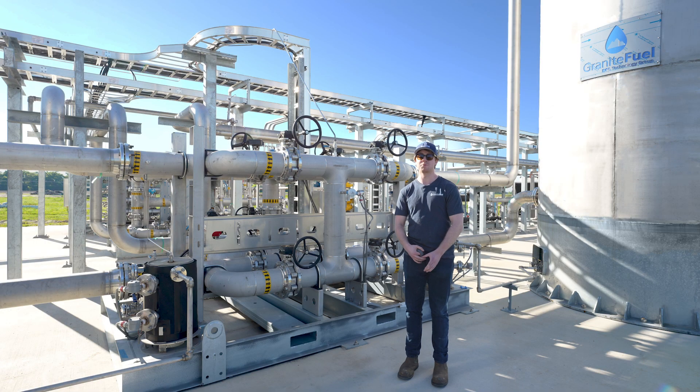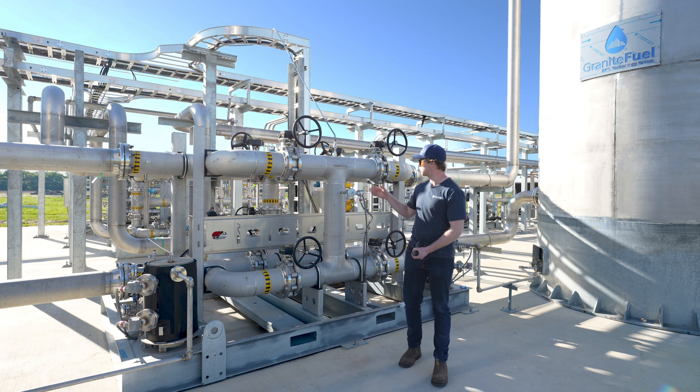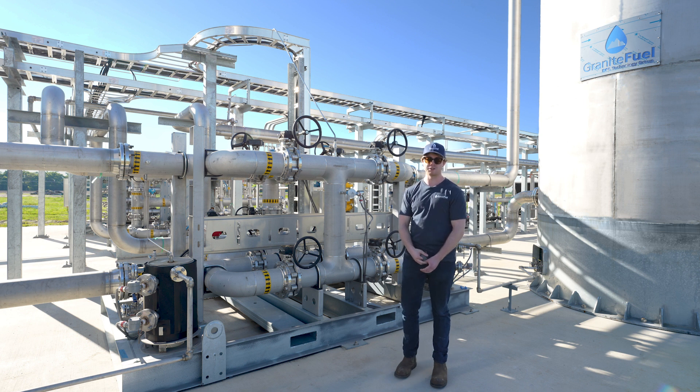For a biogas upgrading plant, H2S removal is typically one of the largest operating expenses they face. To help reduce this, Granite Fuel offers an O2 injection system coupled with our H2S removal solutions. By injecting pure oxygen into our H2S lead-lag valve skid, you can actually prolong the life of your H2S removal media and regenerate spent media, saving our customers money.